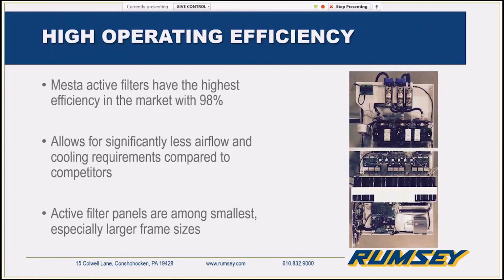Another unique MESTA feature is our high operating efficiency. We have the highest operating efficiency in the marketplace with 98%. This allows for significantly less airflow for our units, and our cooling requirements are a lot less. It helps some of our larger panels be quite a bit smaller than other guys out there. That's a 300 amp panel there, and it's only 27 inches wide, which means our NEMA 1 300 amp unit is actually smaller than many panels that are out there for other manufacturers.